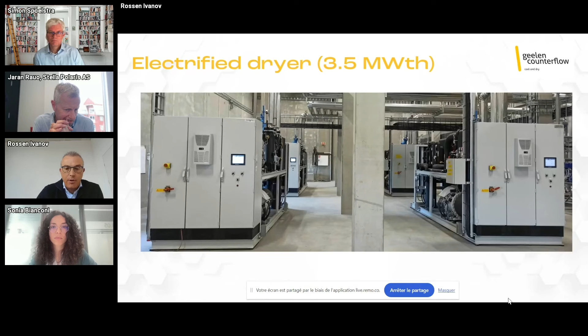What's interesting is to look at the sites beyond dryer applications, where it's relatively straightforward to apply the circularity of heat because sources and sinks are correlated. Things start to be a bit more complex when we look at complete factories. The first point is that cooling systems are significant sources of waste heat. Cooling is about taking heat out, and chillers typically have a COP of 3, so they would produce 3 times more waste heat than their electrical consumption. So plants using refrigerant systems going into deep cooling, such as frozen meat or ice cream, would be significant sources of waste heat. Eliminating cooling towers also helps with the water targets of our customers, because cooling towers are one of the most significant users of water within industrial plants.